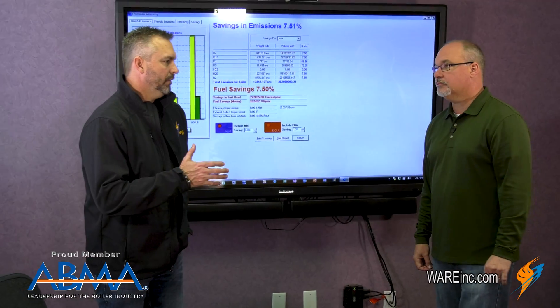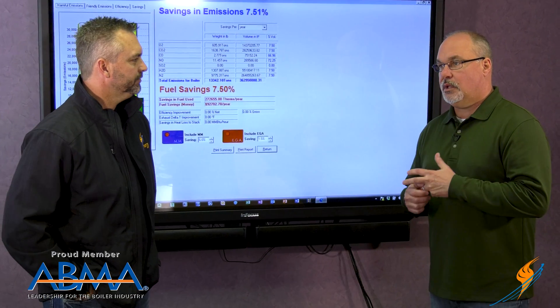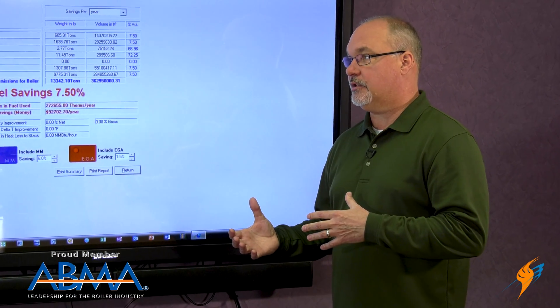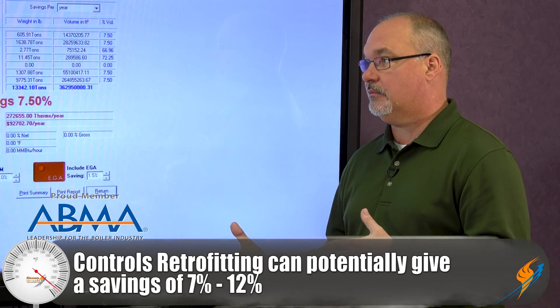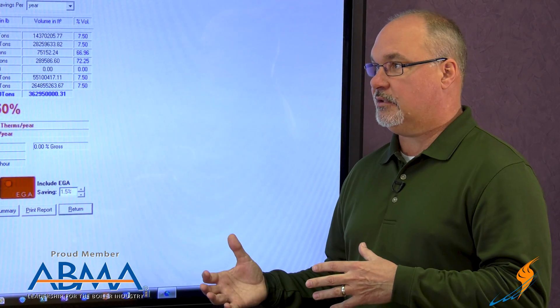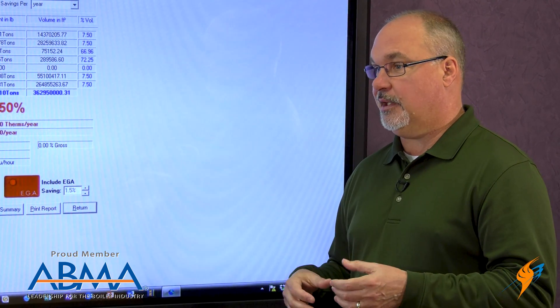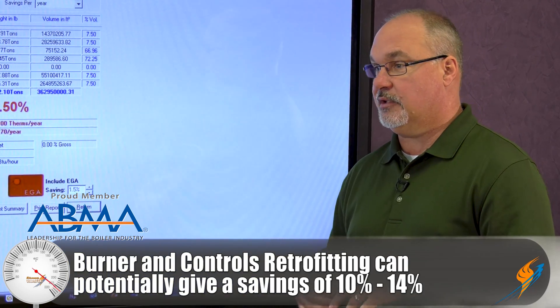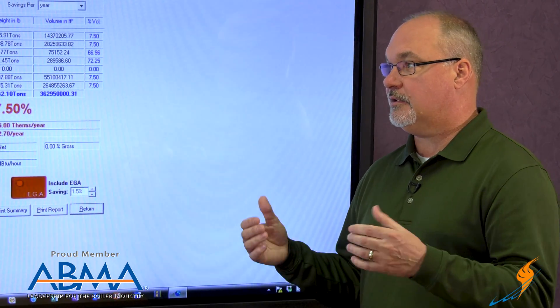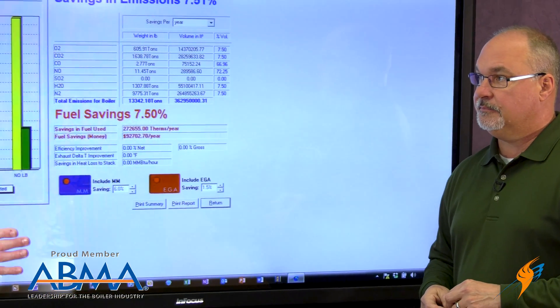With some of the retrofits or even new systems, what are some of the savings customers are actually getting? Our experience, depending on the level of retrofit — sometimes it's just controls — controls can have a great impact on the system. They might be anywhere from potential savings of seven to twelve percent. The limiters become what we're putting those controls on. If we upgrade the combustion systems themselves and have the controls package, and we know the performance the burner can actually do, those savings can be ten to fourteen percent. We've seen them even higher, though we try to be conservative. We've done case studies, seen numbers in those ranges, and we've got hundreds of them in the field. We know that linkage to linkage-less, we get savings.